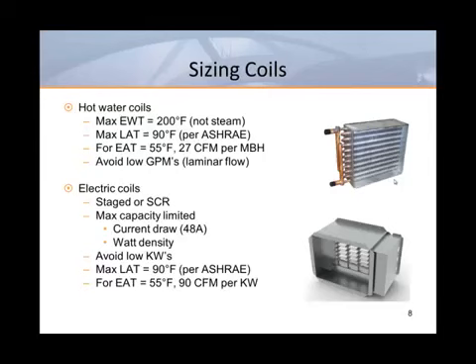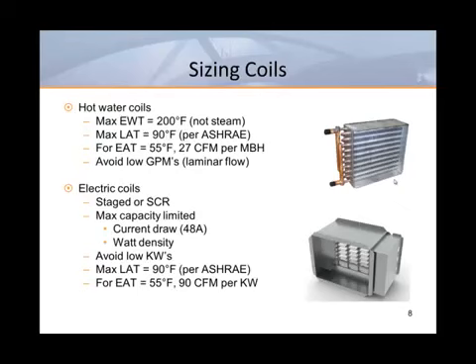So if we wanted a 75 degree room temperature, we should limit our discharge temperature to 90 degrees. If we assume 55 degree supply air, then we would likewise limit the temperature rise through our coil to 35 degrees. This means that we should have at least 27 CFM per MBH to limit our discharge temperature. In hot water coils, it's important to avoid low water flow. If water moves too slowly through a coil, it can go from a desired turbulent flow to a less efficient laminar flow. It's much better to move water more quickly through a single row coil than to move it too slowly through a multi-row coil.